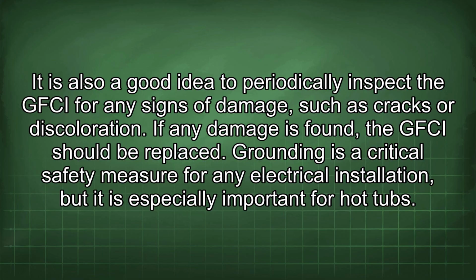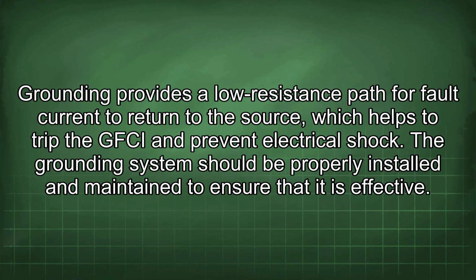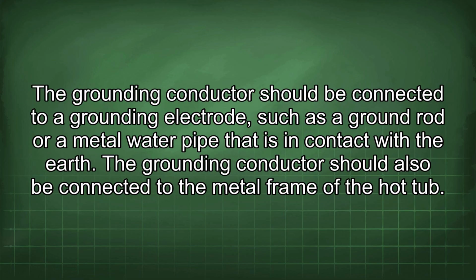Grounding is a critical safety measure for any electrical installation, but it is especially important for hot tubs. Grounding provides a low-resistance path for fault current to return to the source, which helps to trip the GFCI and prevent electrical shock. The grounding system should be properly installed and maintained to ensure that it is effective. The grounding conductor should be connected to a grounding electrode, such as a ground rod or metal water pipe that is in contact with the earth. The grounding conductor should also be connected to the metal frame of the hot tub.